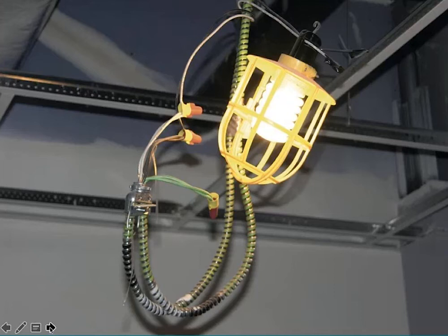Now this goes back to Article 590 where it talks about you don't have to have boxes on your splices for temporary wiring. The concept is it's going to be removed eventually, so you keep your splices up in the ceiling out of harm's way, and you don't have to put them in a box. When you're using MC cable, oftentimes equipment grounding is accomplished by continuity of the armor, if it's AC cable especially.